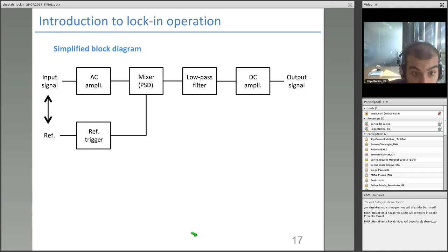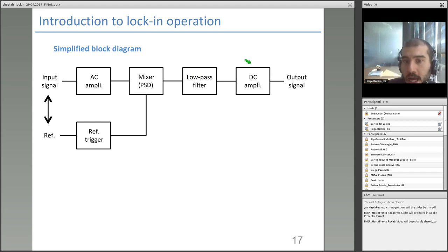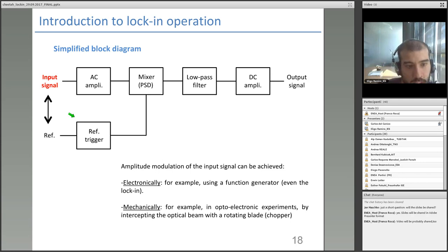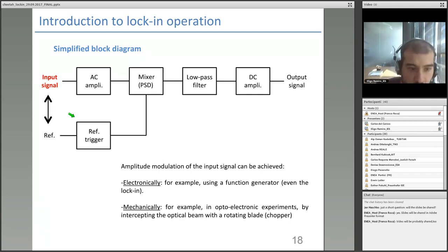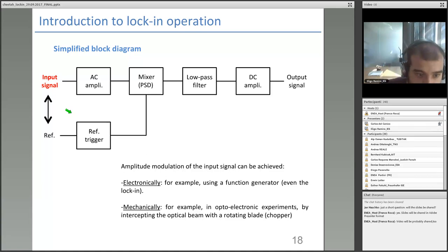Here is a simplified block diagram of the lock-in that we will use throughout the presentation. Basically, we have the input signal to be measured, which will be amplified inside the lock-in. Then there is a mixer or PSD (phase-sensitive detector), a stage of low-pass filtering, DC amplification, and finally the output signal. There is also a box called the reference trigger, which we will discuss shortly. The lock-in works with AC signals, not DC — so the input signal must already be oscillating when it reaches the lock-in.